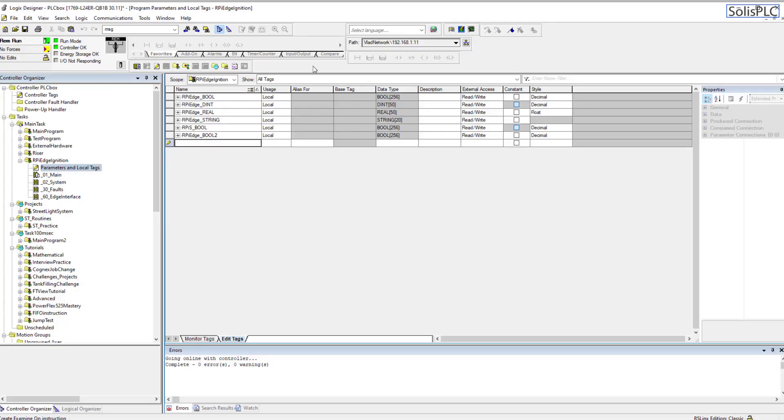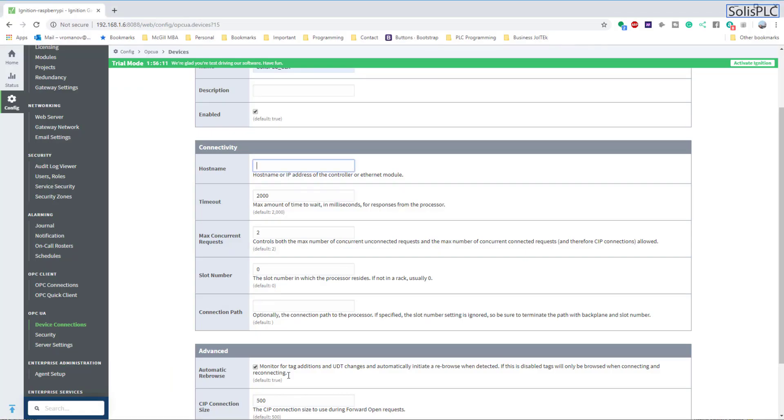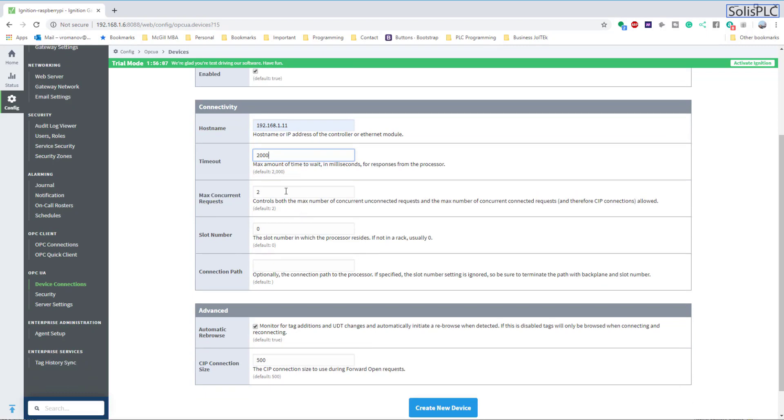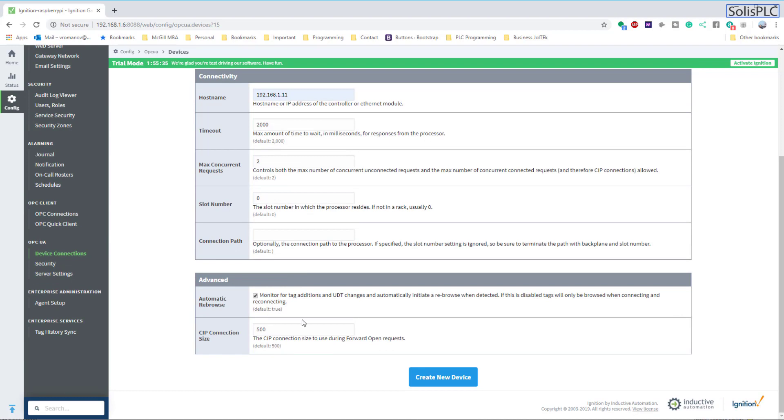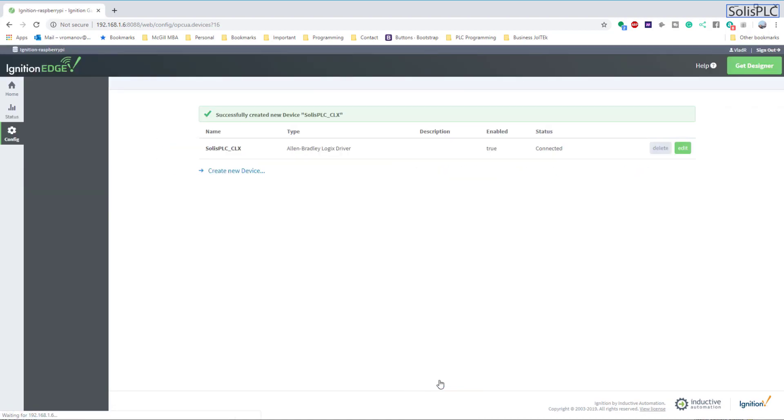Next we're going to give the IP address. Of course, our Raspberry Pi which hosts the Ignition Edge needs to know exactly where the processor is located. If I switch back to the processor, you'll notice that the IP address is listed right here. It's also listed on the spreadsheet that I've shown you a couple of videos ago, and so we can put that into place. There's going to be a few more options - I am not extremely familiar with them but we can just read the description. The maximum amount of time to wait for responses from the processor - we can definitely leave it at the default for now. Two requests. Slot number zero - this is important if you're using not a CompactLogix but essentially a ControlLogix PLC, then it's going to be different depending on which PLC you're connected to. Optionally there's going to be a path. We are connecting directly, once again, and that seems to be fine. So we're going to create a new device.